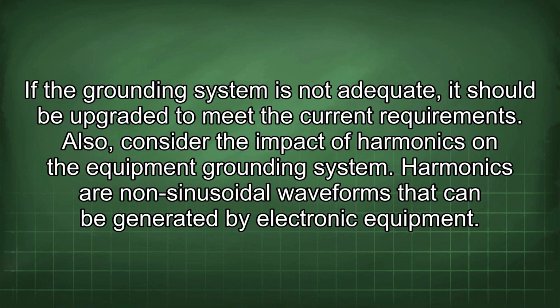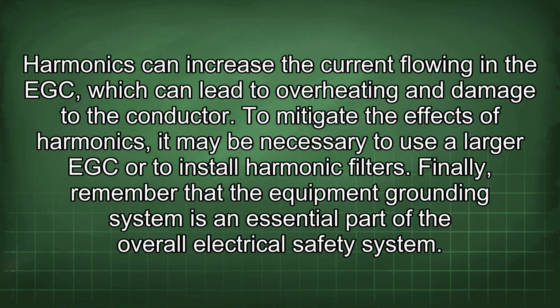Harmonics are non-sinusoidal waveforms that can be generated by electronic equipment. Harmonics can increase the current flowing in the EGC, which can lead to overheating and damage to the conductor. To mitigate the effects of harmonics, it may be necessary to use a larger EGC or to install harmonic filters.